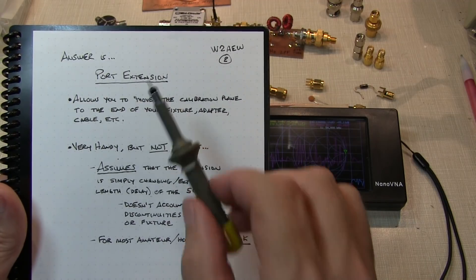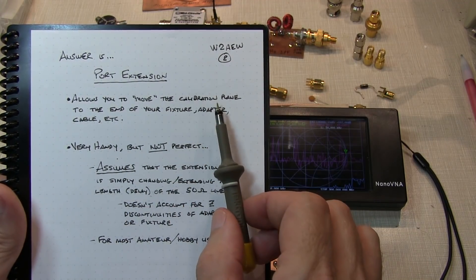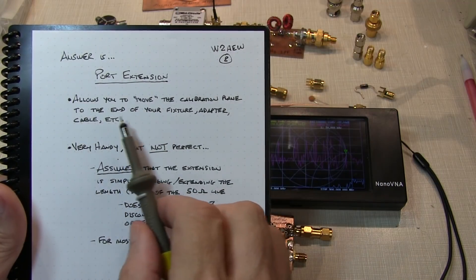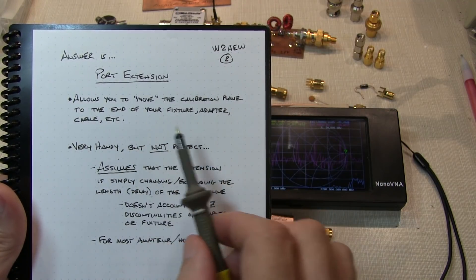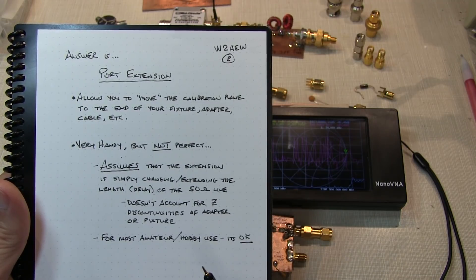Well, the answer is to use a port extension. This allows you to move the calibration plane, or extend it, to the end of your fixture, cable, adapter, or whatever it is that you needed to add in order to connect your DUT.